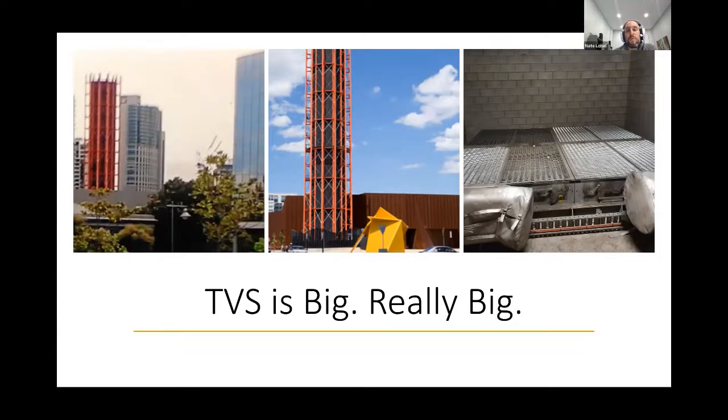I've worked on one where I think at a station we ended up with over 300 meters cubed per second of air movement in fire mode. As an example, on the right here is an existing ventilation duct for a road, actually a bus transit system. It's about 4 or 5 meters by 4 or 5 meters, and there are 2 or 3 more of these just adjacent to it for this station.